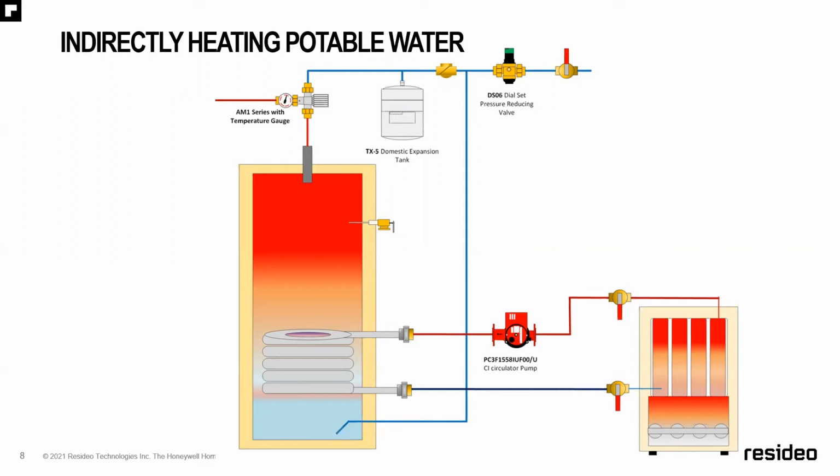I've had a situation back in Colorado where it was a multifamily project, and they had a couple of TurboMax water heaters, and I would get the call first thing in the morning. The first person that takes a shower gets a hot shot. It's like 160 degrees coming out of there.